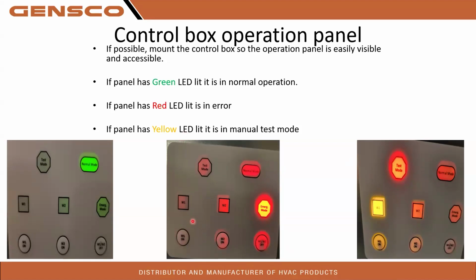Find out what this little LED panel is doing. If it's lit green, then your IntelliHeat is in normal operation, no error. If their gas furnace is running, it could be because of the economic balance point or the comfort balance point. Comfort balance point, it'll learn at what ambient temperature it takes to heat the house, and it'll automatically switch over to the gas furnace. Or if it's been running for more than 20 minutes without a temperature change, it'll switch over to the gas furnace. So you'll see the gas furnace running, normal operation. If your gas furnace is running and you have a red light right here, emergency mode, that tells you the system is in error. Okay, so if that's the case, you need to go look at your heat pump, start trying to figure out what the error is, look for any codes on the thermostat. If you have an MHK thermostat or a Mitsubishi thermostat, take a look there, or go look at your heat pump for any error codes out there.